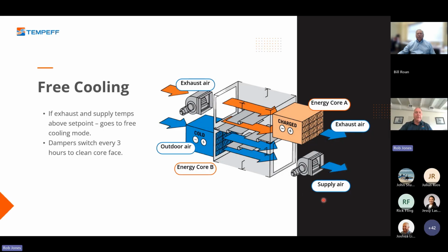It will do this up to 3 hours before it will direct the air the other way, and that's so that the cores can self-clean themselves. Just like our 60-second cycle, every time it switches, it blows off any dirt or debris that's been captured on the face of our heat exchangers. So they literally self-clean themselves.